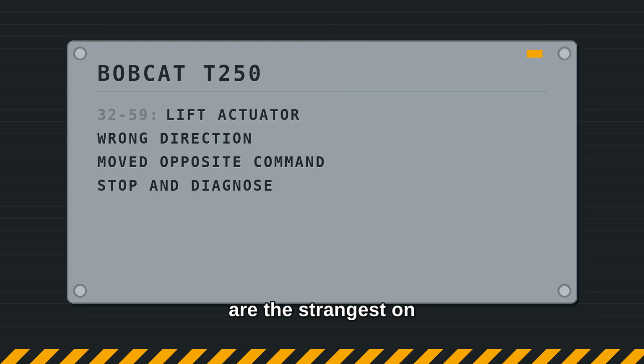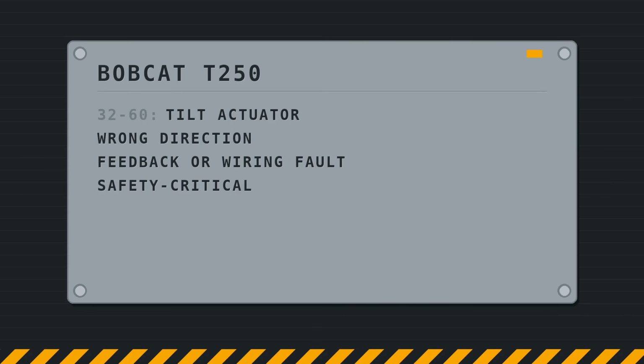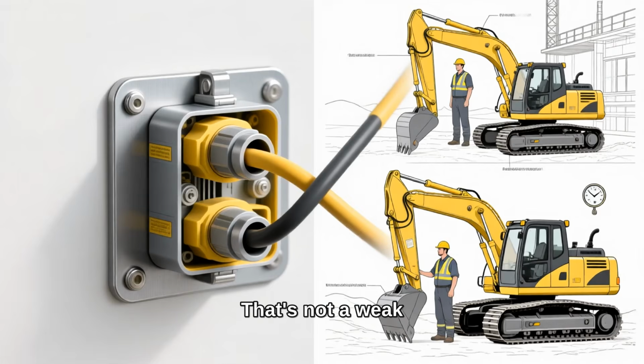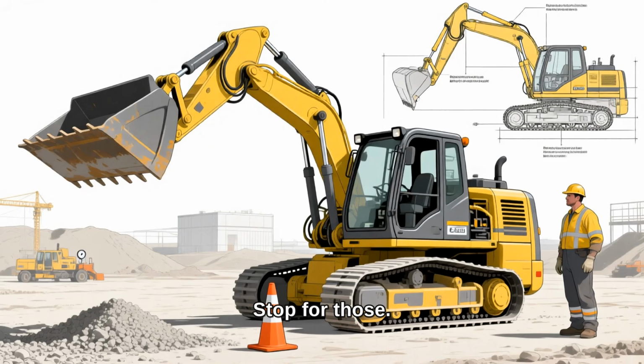And the last 2 were the strangest on the whole list. 3259, lift actuator wrong direction. 3260, tilt actuator wrong direction. The actuator moved, all right, the opposite way from what was commanded. That's not a weak part. That's wiring or feedback handing the system a very confident lie. Stop for those. A control that argues about which way is up isn't a nuisance code, it's a safety problem.